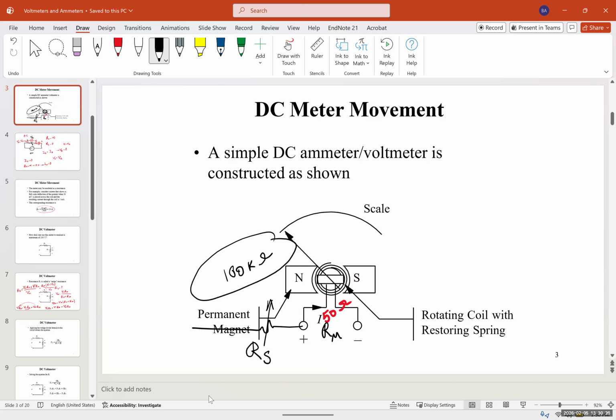And also, after repair, you have to calibrate it. You have to find the exact same coil. So it's not a straightforward, easy task. Now here you can see the screw. Can you see the screw when I change it? You can see I can change and calibrate it. You can see the calibration with the screw. I can calibrate it back to 0. Okay. Some of them have it also on the back, and calibrating is not an easy task.